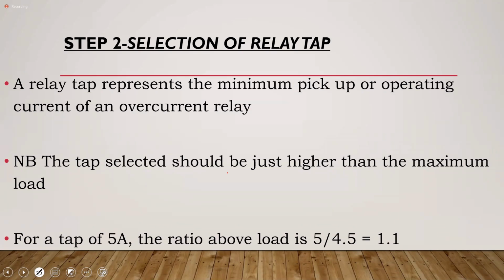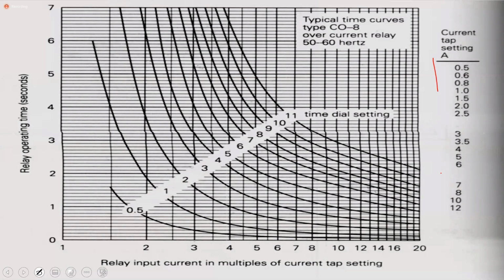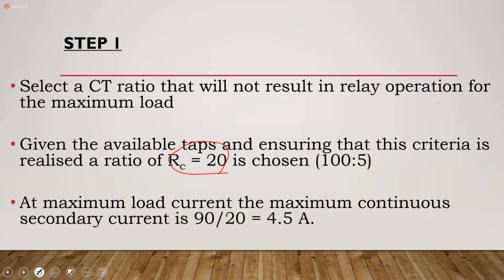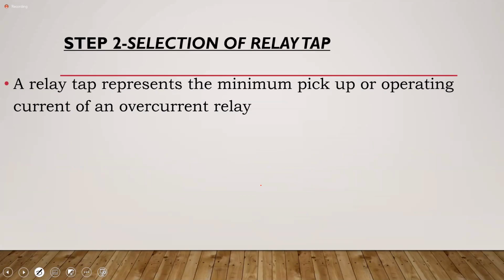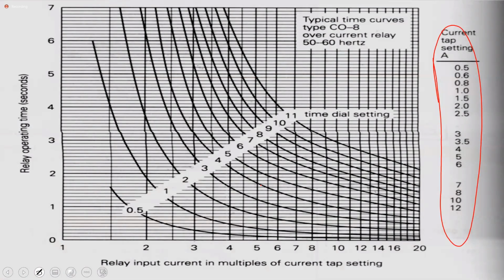Why am I selecting a tap of 5? It is because when I look at the output curves for the relay, these are the available taps. When I divided the 90 by 20, I get 4.5. So when I now come to the curve, I have 4. I can't select 4 because if 4 amperes come from the CT, what that would mean is that the relay would operate when I want to supply my maximum load, which is 90 amperes. Is that clear? Talk to me.